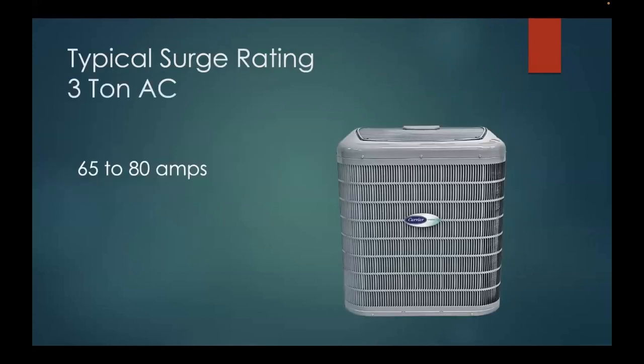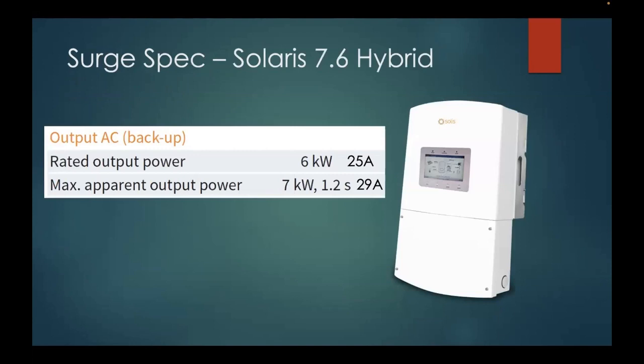Okay, everybody with me? Let's take a typical surge rating of an air conditioner. Unfortunately there's no typical number, but it's a range—65 to 80 amps. That's a long way from 29 amps. So if we take 65 divided by 29 amps, you'd need 2 battery inverters just to start it. Worst case, 80 divided by 29 is 2.75, meaning we'd need 3 of these battery inverters just to start that air conditioner.